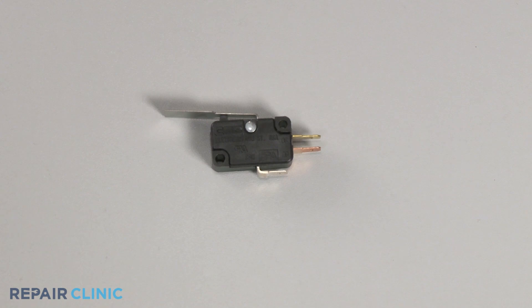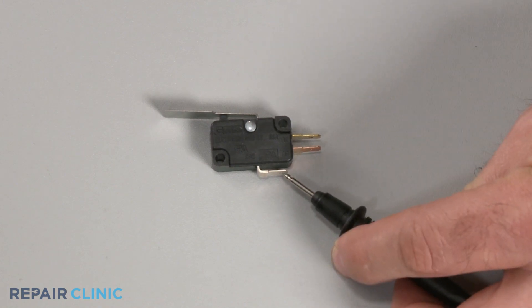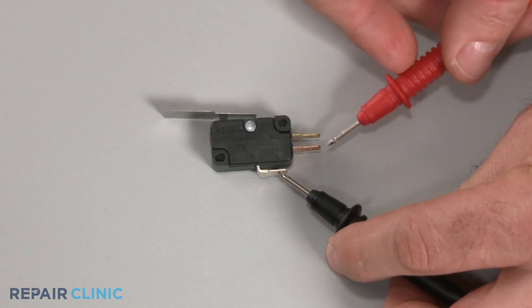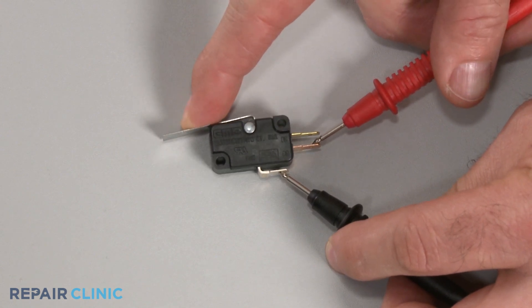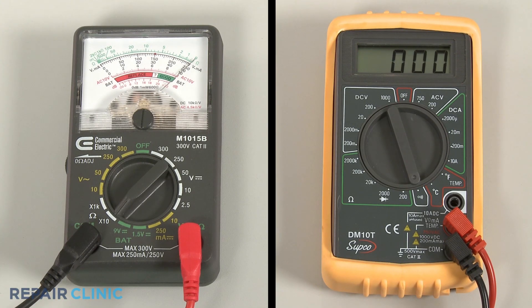To test the switch, use a probe to touch the common terminal and the second probe to touch the normally open terminal. Now actuate the switch. If the meter reading shows zero ohms of resistance, the switch has continuity.